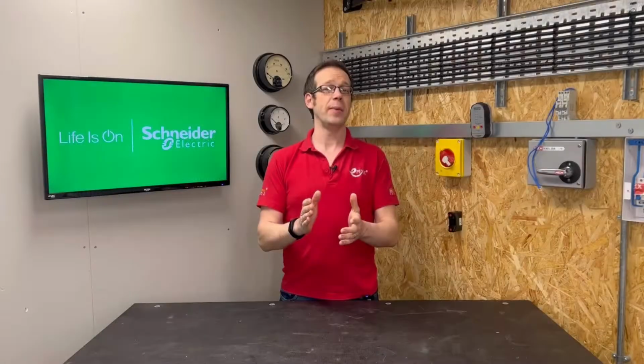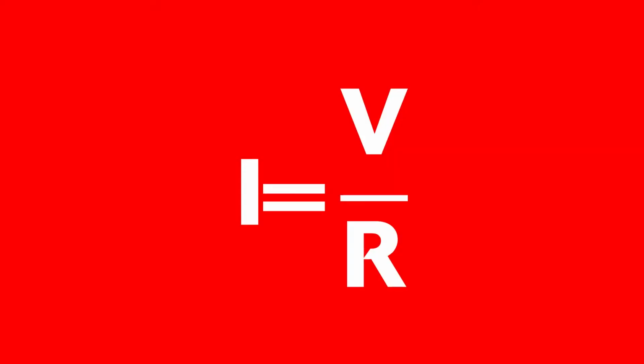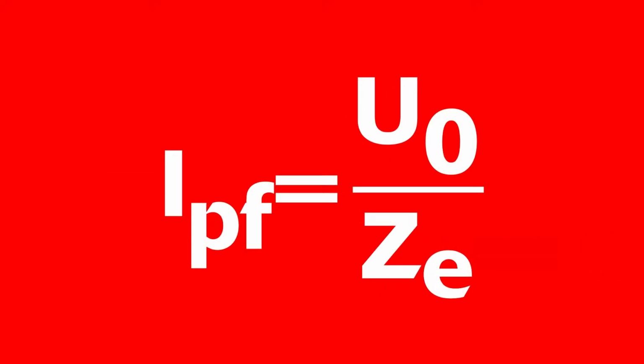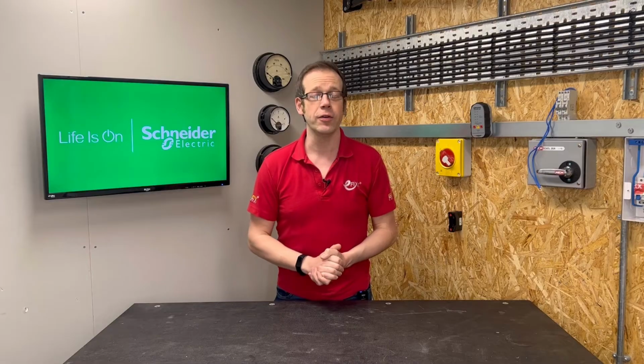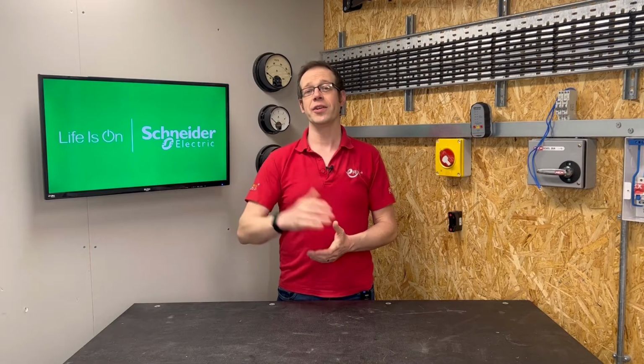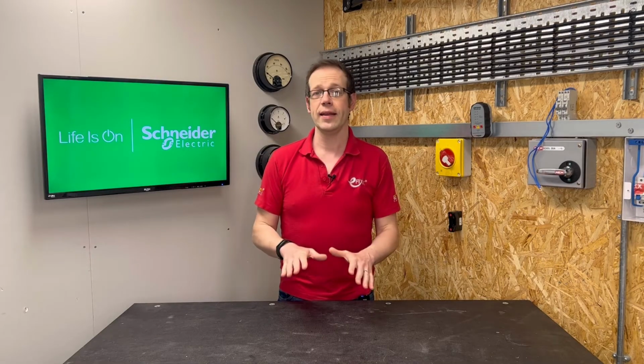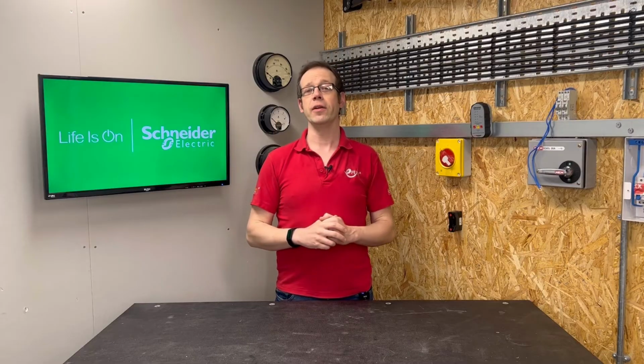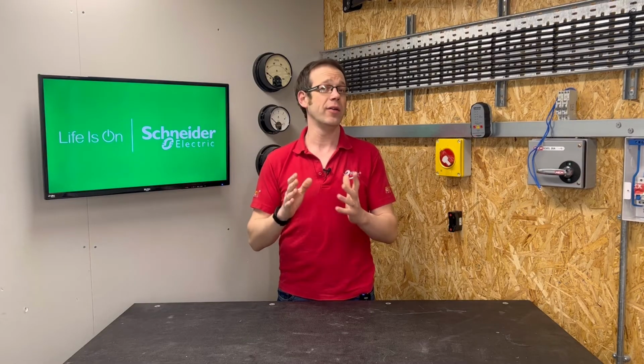If we go back to our basic principles and apply a bit of Ohm's law, we know that the current that will flow is directly related to the resistance, or in this case the impedance, of the fault path. If we have measured the earth fault loop impedance, or Ze, and we know the nominal voltage is 230 volts, we can calculate the expected current that will flow. So while a nice low Ze is great for meeting the earth fault loop impedance values and therefore the disconnection times needed, the lower the Ze, the higher the prospective fault current, which in some circumstances may create other issues.